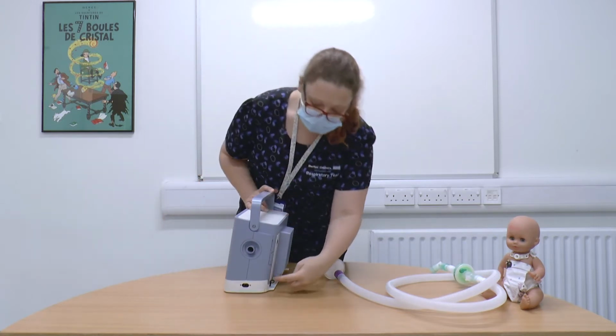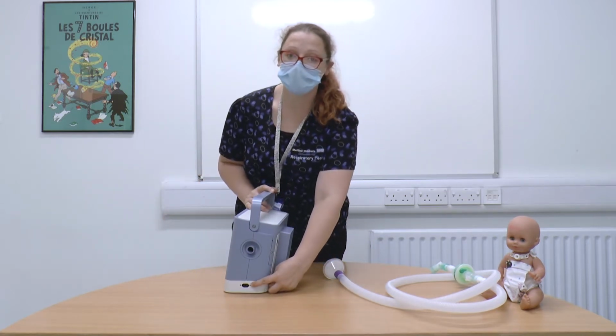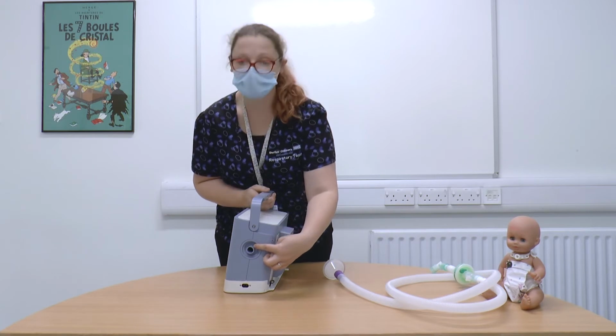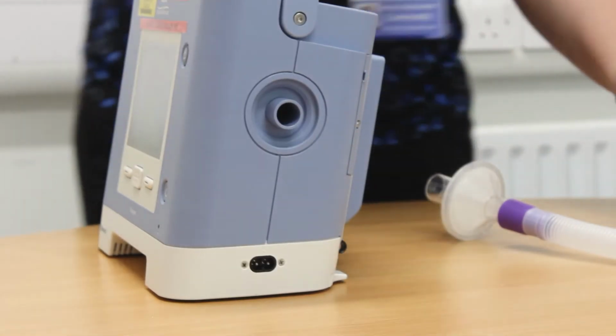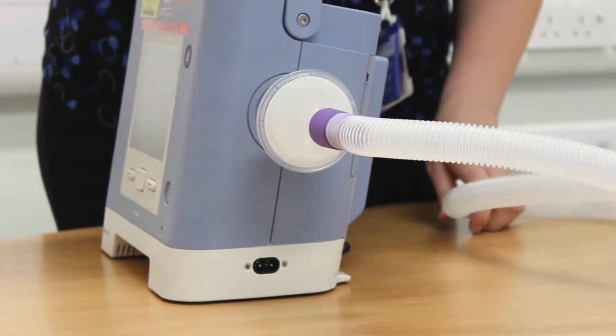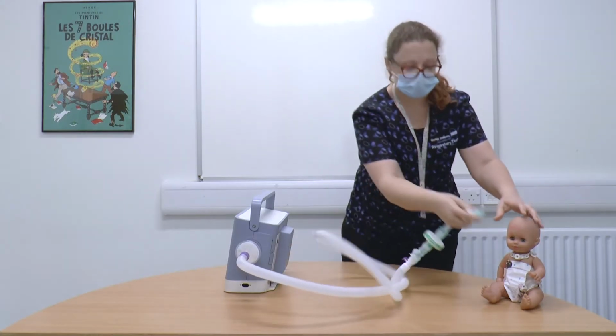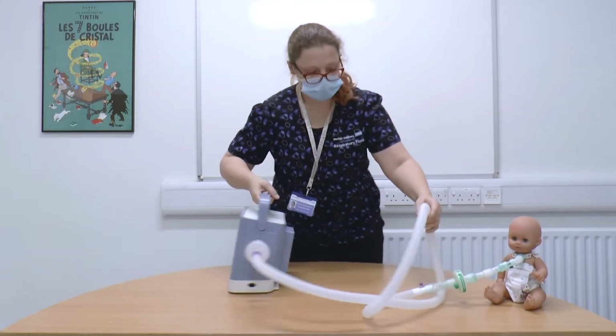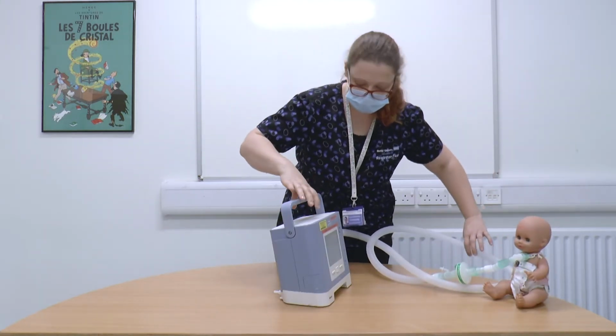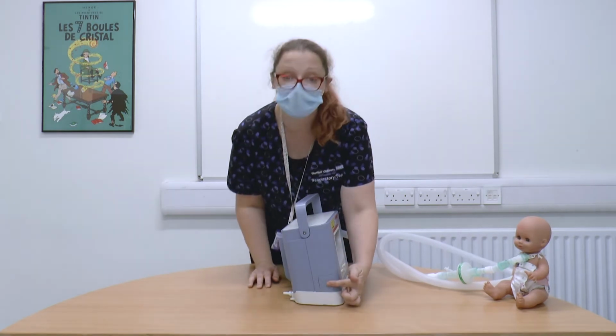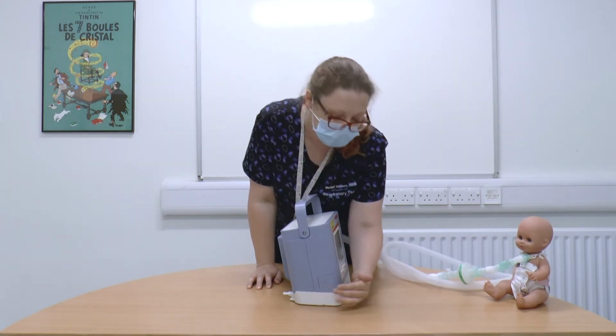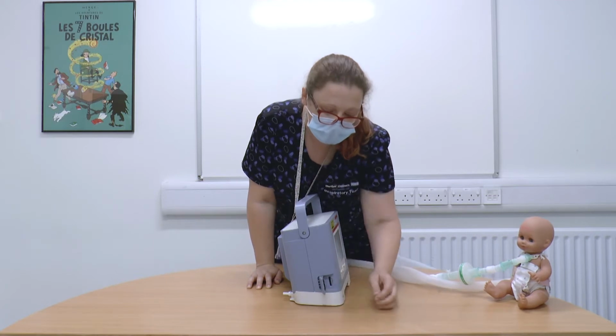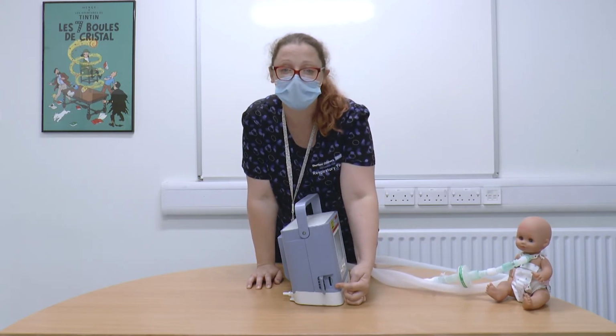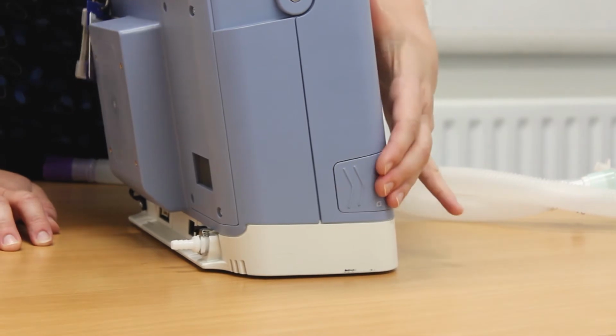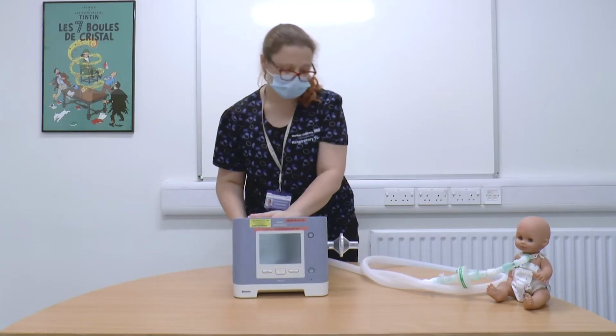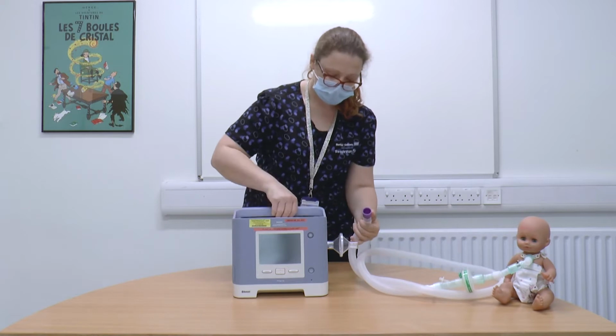The charge cable attaches to the side of the ventilator, and on the same side is where you will have the place to attach your expiratory flow of tubing to the child. On the other side of the ventilator, you will see there are 2 slight arrows. You do not need to worry about this. If you push it, it will open up and there's a slot for an SD card. This is only for use by the ventilation team for us to see the type of ventilation that's been occurring for children.